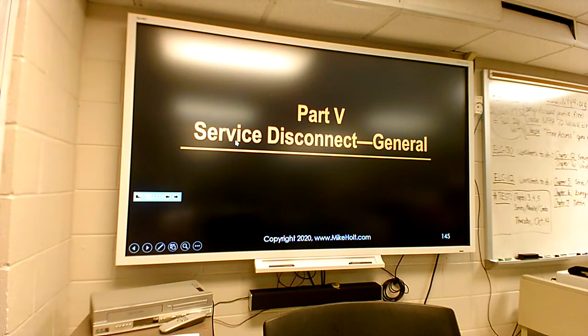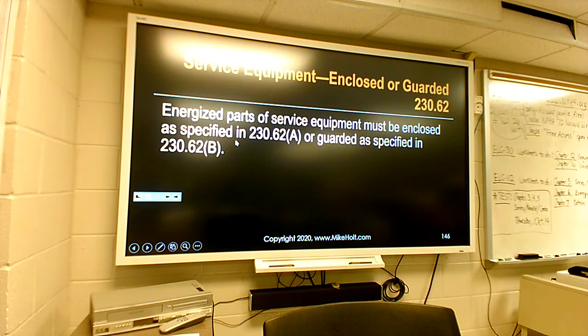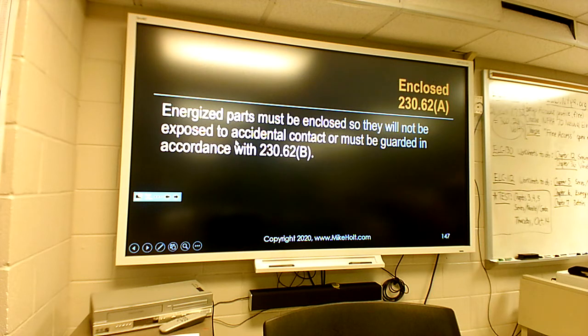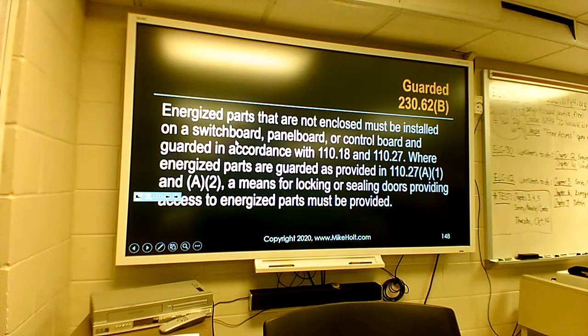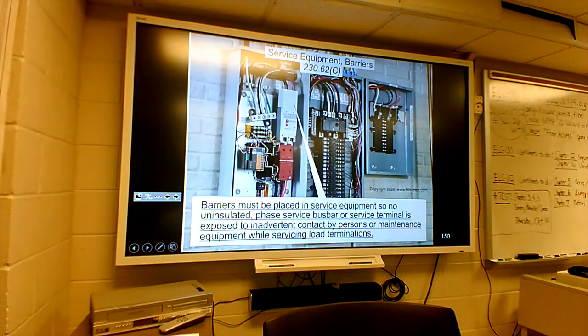Part 5, your service disconnects in general. Your energized parts must be enclosed and guarded. Barriers. Barriers must be placed in service equipment so no uninsulated phase conductor, service bus bar, or service terminal is exposed to inadvertent contact by persons or maintenance during servicing load termination. So see, there's a cover up here.